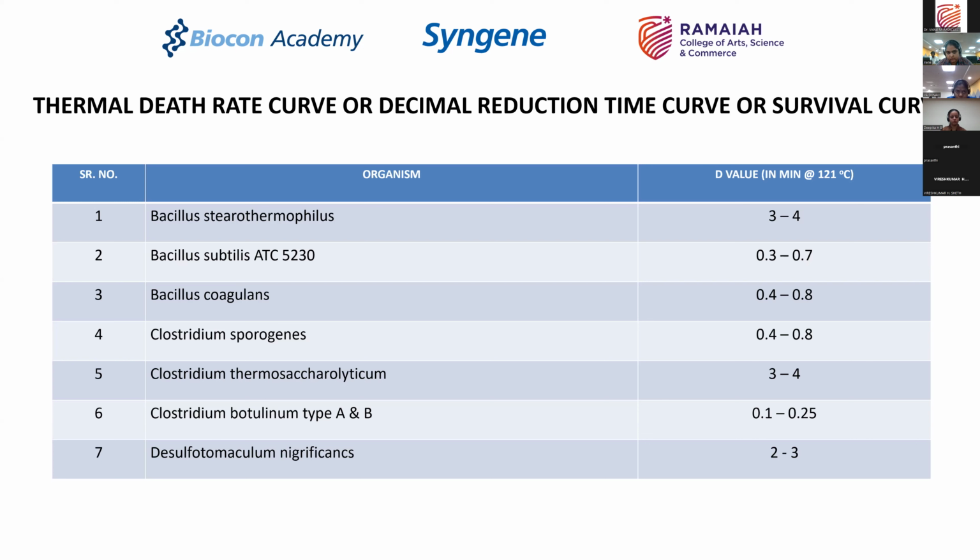Because anyway, that's your biological indicator, which you'll use as per USP to validate your cycles also. So from that perspective, knowing the organism becomes very important. Generally, when you have a sterility failure, you will do a profiling of the microbial organisms present in the environment or in the loads, and characterize them to find out what the microorganism is, what family and what subfamily they belong to, and then based on that you will arrive at a criteria of how to sterilize them.